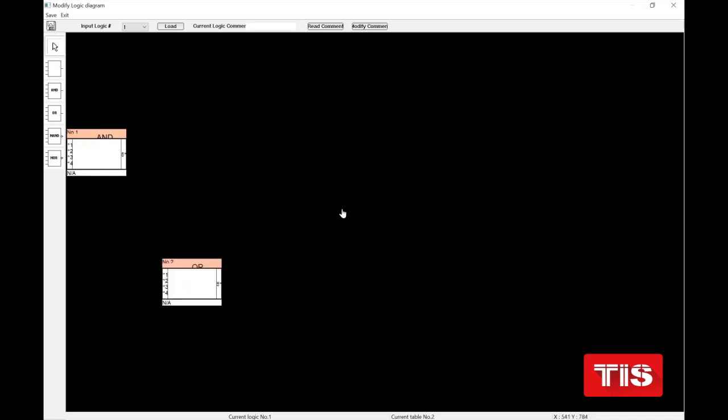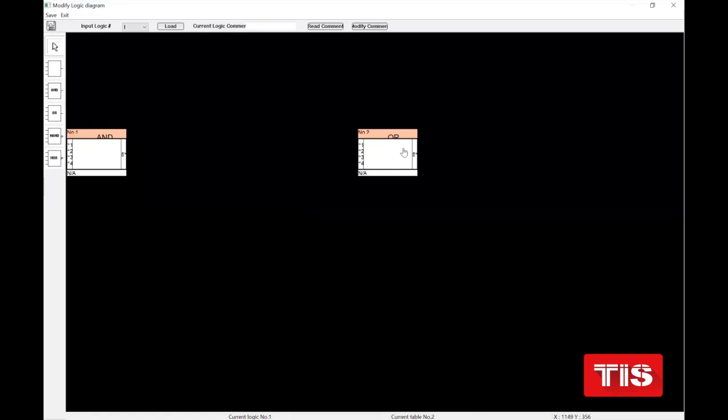But if we choose an or table, it can be Monday or 6 a.m. Therefore, on Friday, Thursday, Saturday at 6 a.m. it will again turn on the light, because in the or table, only one of the pins must be in the correct position. It's very necessary to choose the correct table. It's very necessary.